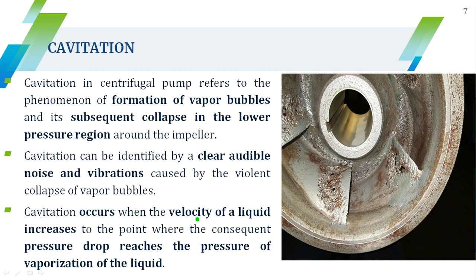Vapor pockets or vapor bubbles are formed in the liquid and then collapse — similar to pricking a soap bubble which bursts outward. This collapse creates shock waves that strike the impeller blades or the casing of the pump, creating damage and holes. The formation of vapor bubbles is very dangerous for the pump and decreases its service life.